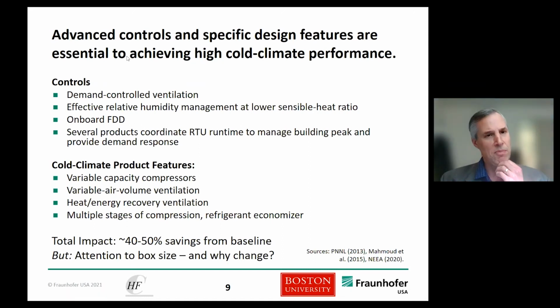You can do a lot of things with controls, demand control ventilation, reducing the amount of outdoor air you take into the building effectively. You can also do things like onboard fault detection and diagnostics. There are some products out there which help with that, although there could be much more of that done and more faults addressed by those products. And then there are things that coordinate packaged rooftop unit operations among units for the same building owner to provide coordination and manage the peak load, and provide demand response services. So things are available to help do this. And if you look at the cold climate features, besides getting down loads and managing peaks and more effectively providing grid services, people can do things around variable capacity compressors.